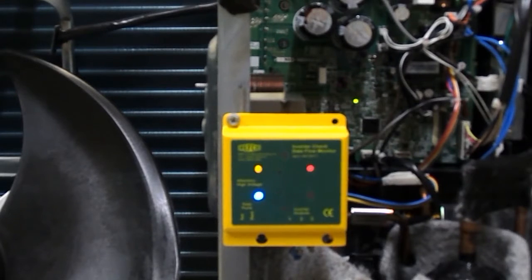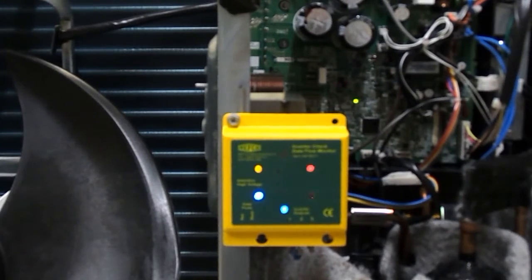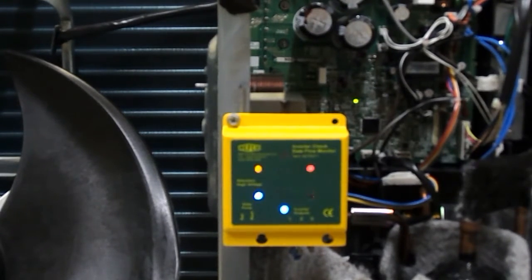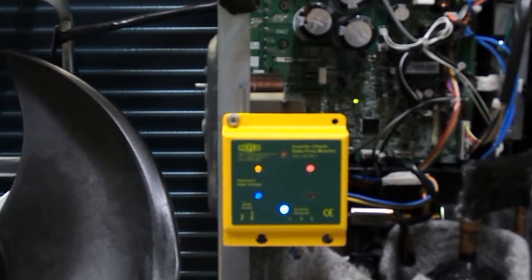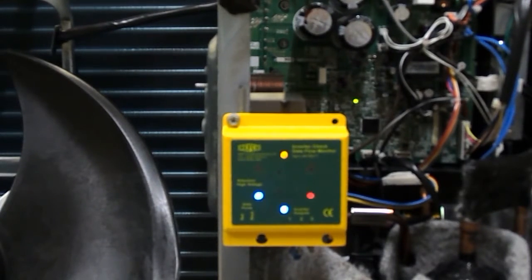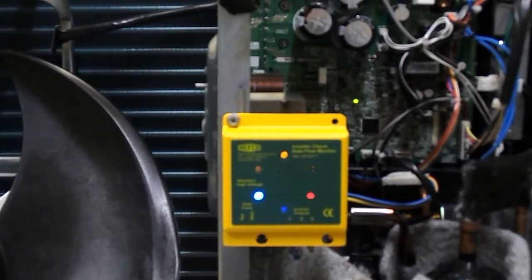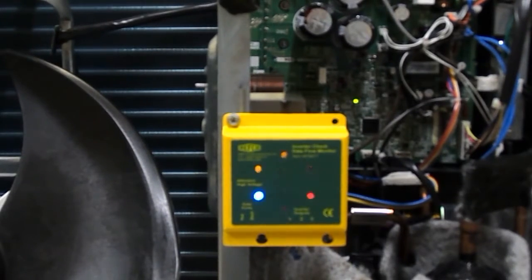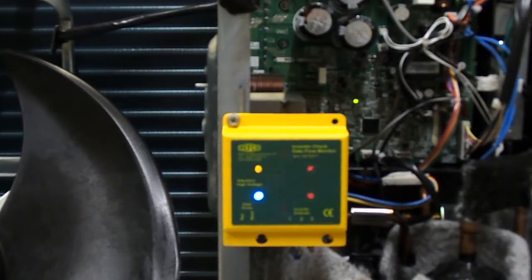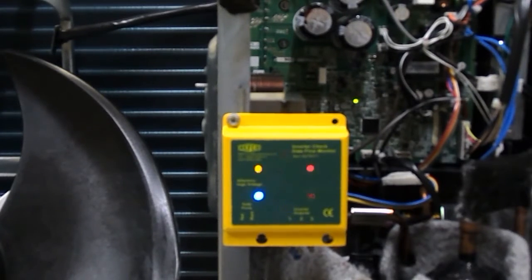This is actually staying on a lot longer than normal because this particular unit has a function to test the transistor in a special mode, which allows the output to continue without it shutting down. If you don't have this, typically this test would take less than six seconds because the board is looking for a feedback signal from the compressor.